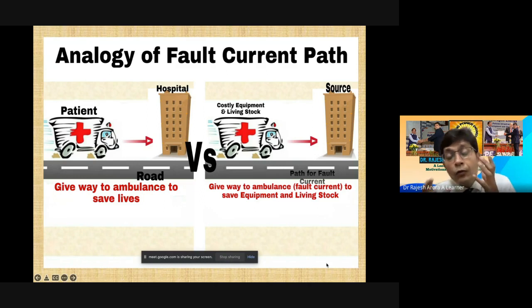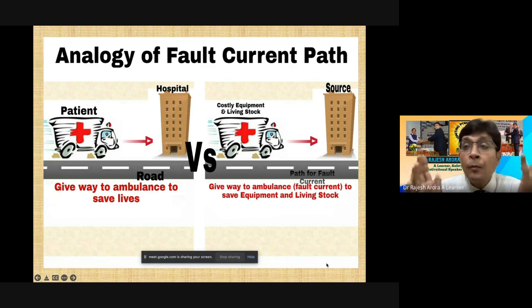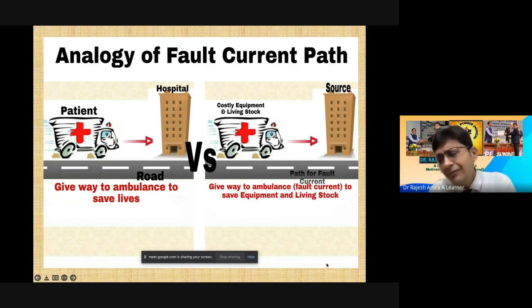Here, our costly equipment and my livestock are my patient at the time of fault. We have to give some dedicated path so that the current can reach the source in minimum time, and we can save costly equipment and living beings, and we can avoid fire. Because when you are not providing the proper path, there is high resistance, high voltage, high arcing, and it may lead to any disaster and delay in operation of your protection system. We have to be very much careful.